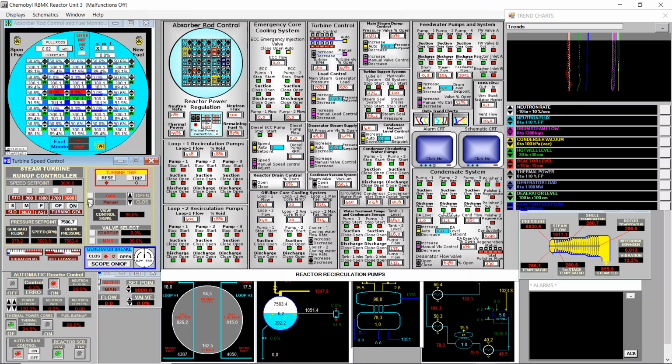I will switch to manual now and open the main valve to 100%, hoping that the pressure set point doesn't drop too much. You see when I switch to manual, this vibration disappears because the valve stops opening and closing to keep the pressure. I don't think this opening and closing is very good for the turbine blades. Look now, so smooth. Generated load going up.